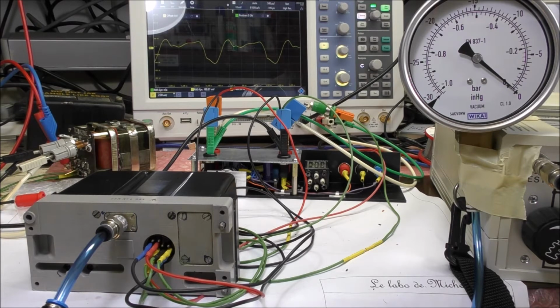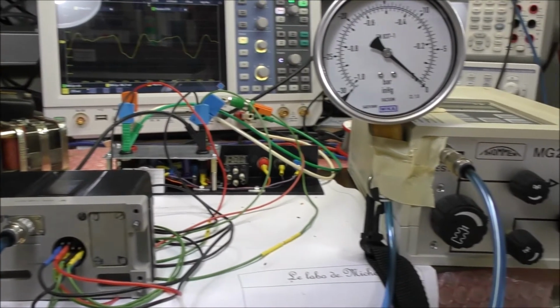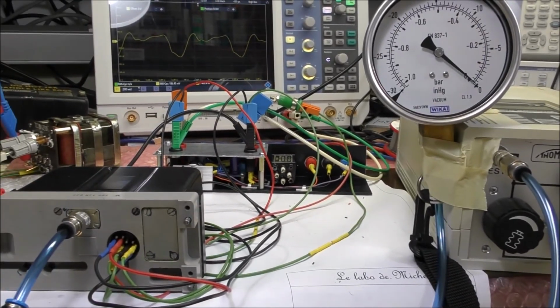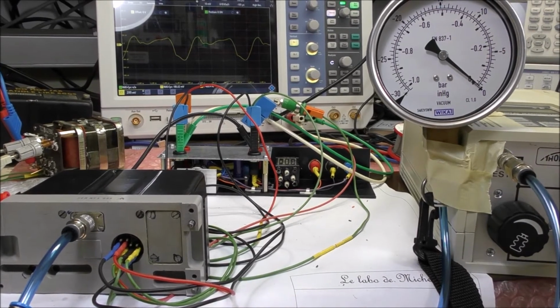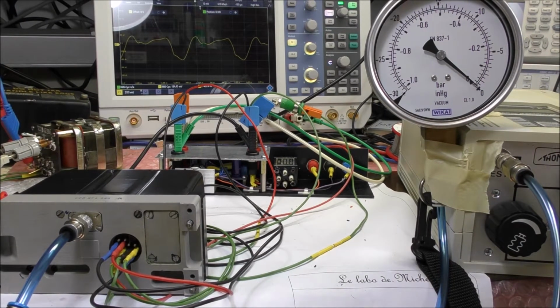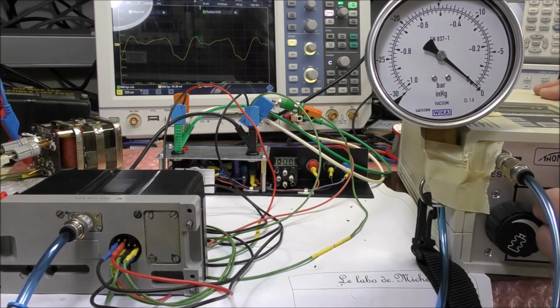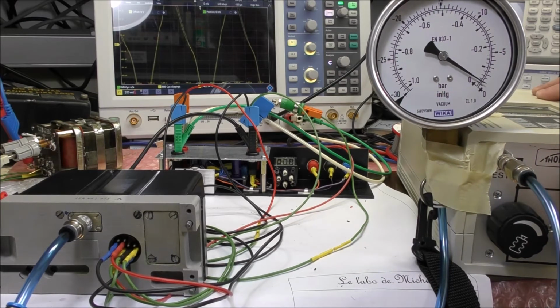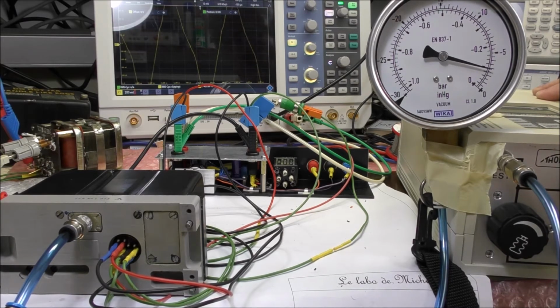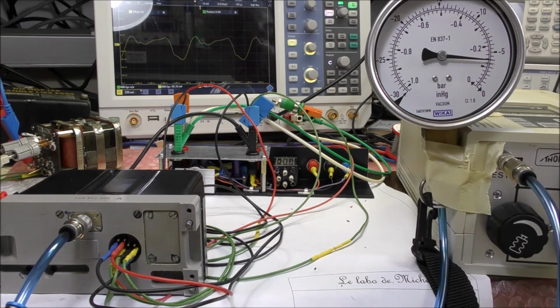Okay, so I have connected this transducer to the air pressure generator, which is on the right here. I have a manometer here which permits to measure the pressure, which is below, of course, the outside pressure. So the pressure is negative relative to the room pressure here. So I will start. Okay, you can see that we have an effect. And there is no leakage, or maybe very little, but I cannot see it on the manometer. You can see that the servo control loop works.